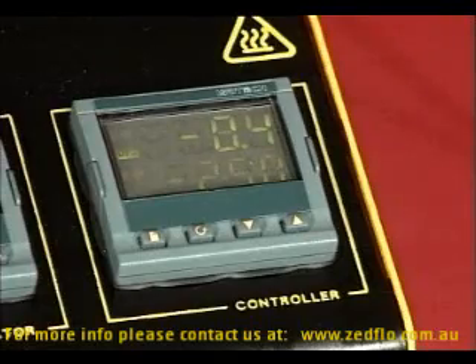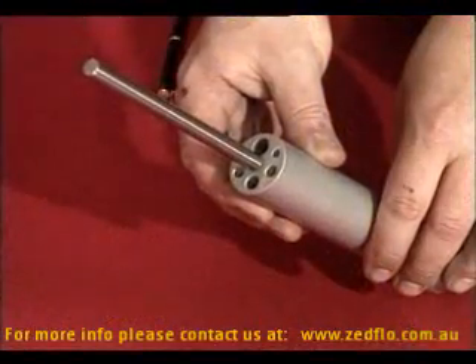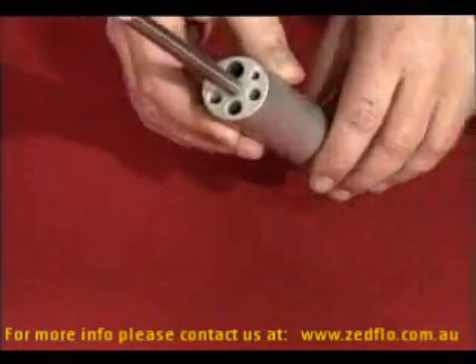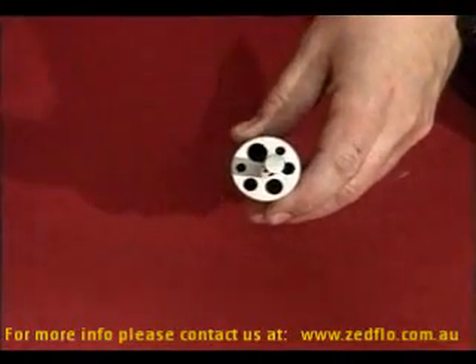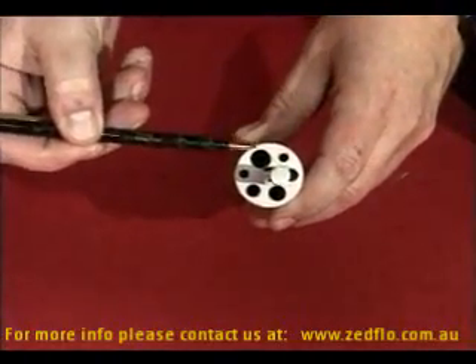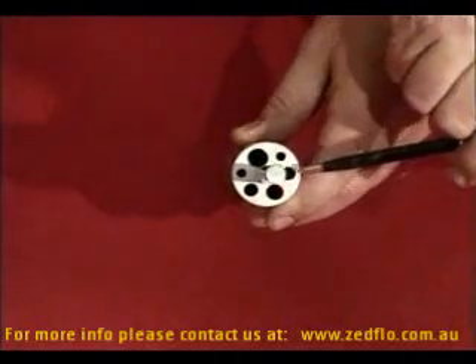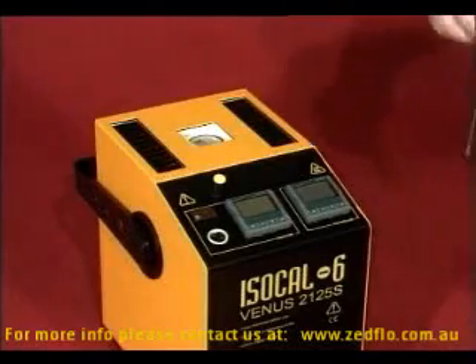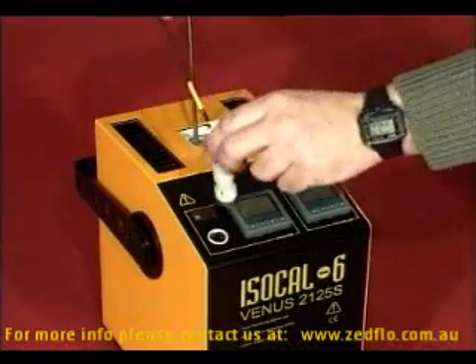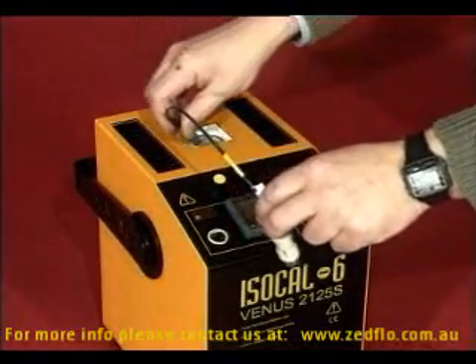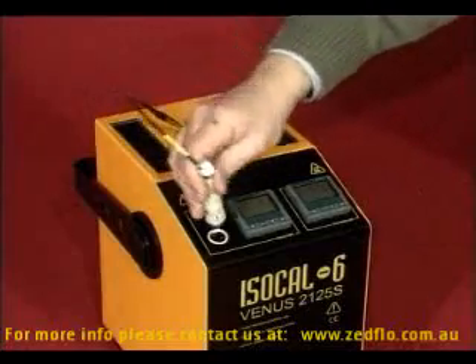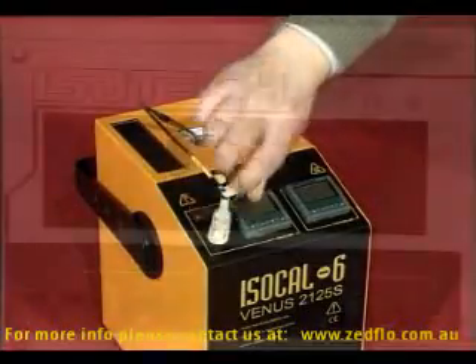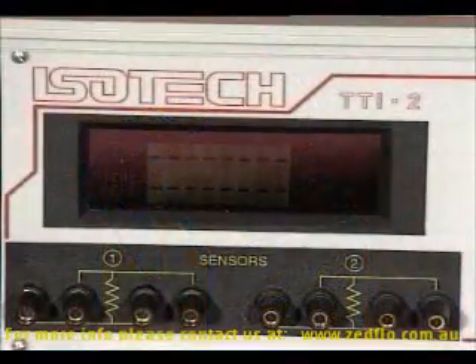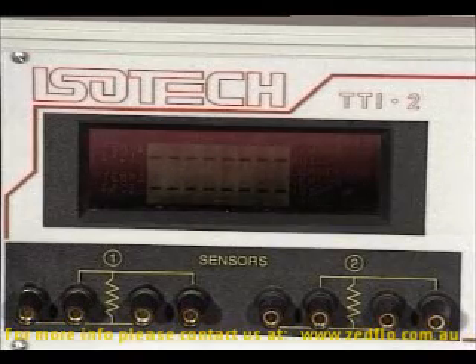The calibration volume can be used in a variety of ways, and each should be considered on its own. This is an anodized aluminium insert designed to fill the calibration volume. It is drilled with 6 holes designed to accept various industrial temperature sensors and the calibrated working standard. The working standard thermometer can be connected to an indicator built into the Isocal 6, which is called a sight version, or it can be connected to a separate indicator such as Isotech's TTI-1 or TTI-2.